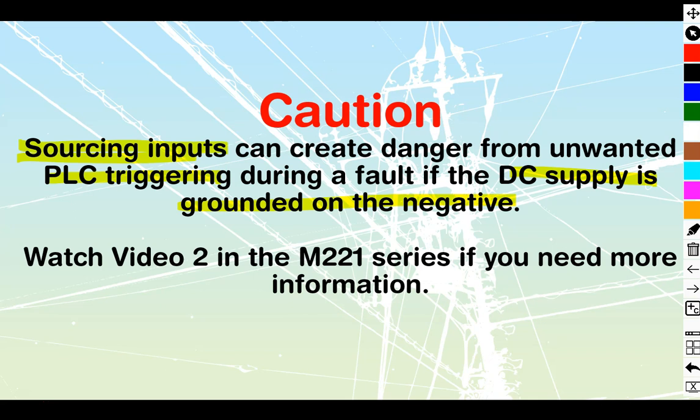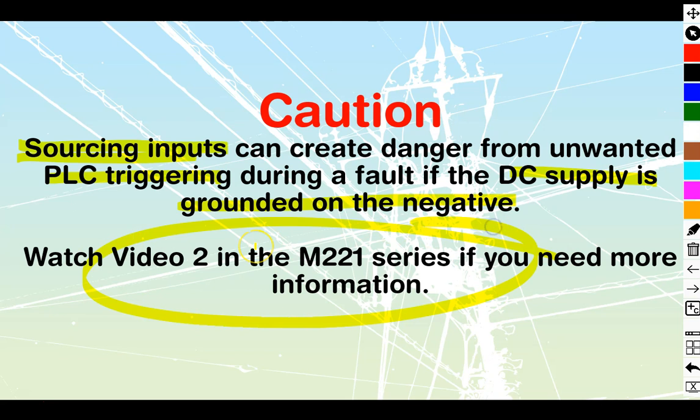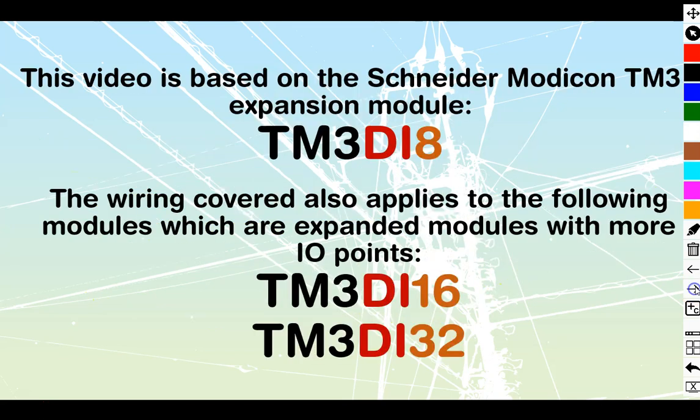So if you do decide that you want to go with sourcing inputs, or if somebody's forcing you to go with sourcing inputs, just be knowledgeable of the fact that they can cause fault. They will not cause fault in and of themselves. However, if there is a ground fault that exists on the system somewhere, then we do get these problems. So if you need more information, you can go watch video number two in the M221 series. It's a full 20-minute video on sinking, sourcing, and IEC positive and negative logic.